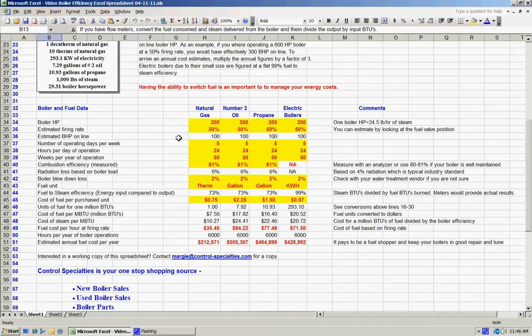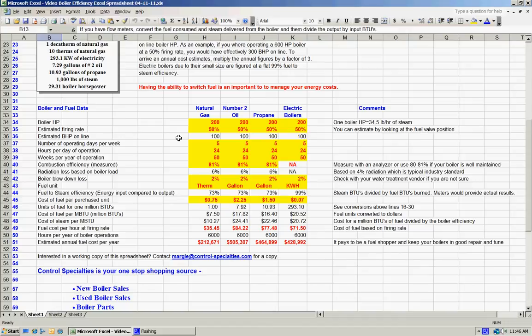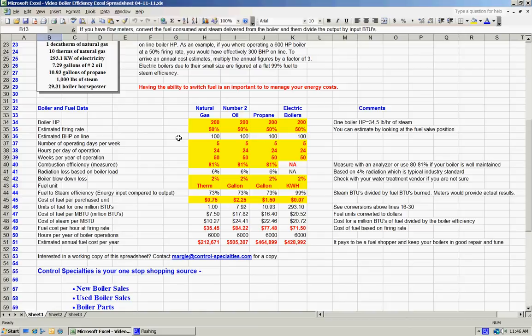So as an example, if you had a 600 horsepower boiler, and you're operating at a 50 percent firing rate, then your net delivered horsepower online would be about 300. So if you took my figures and tripled them, you'd get pretty close to what your boiler would actually be doing. There are some issues having to do with radiation losses and how the boiler is loaded that ultimately will affect the fuel to steam efficiency, but for the sake of a first analysis, that'll get you close enough.